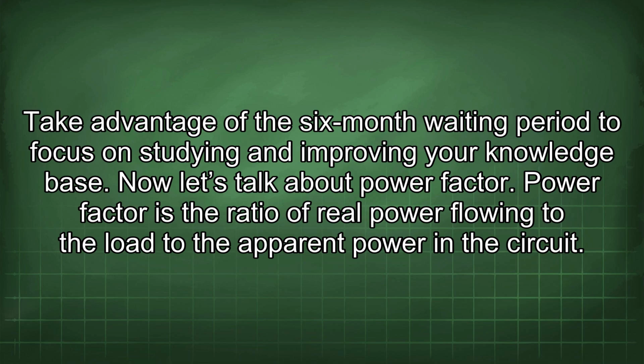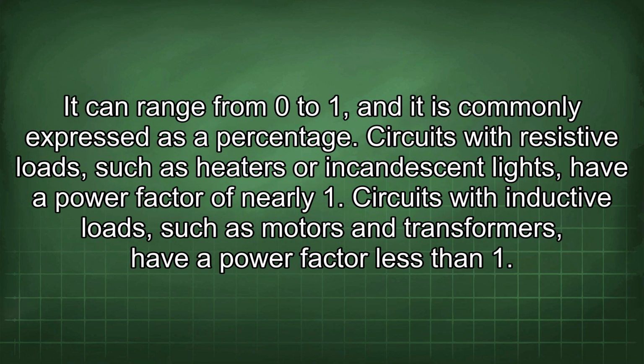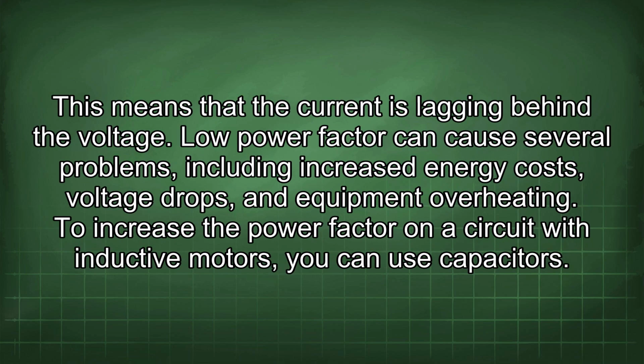Now let's talk about power factor. Power factor is the ratio of real power flowing to the load to the apparent power in the circuit. It can range from 0 to 1, and it is commonly expressed as a percentage. Circuits with resistive loads, such as heaters or incandescent lights, have a power factor of nearly 1. Circuits with inductive loads, such as motors and transformers, have a power factor less than 1. This means that the current is lagging behind the voltage. Low power factor can cause several problems, including increased energy costs, voltage drops, and equipment overheating.